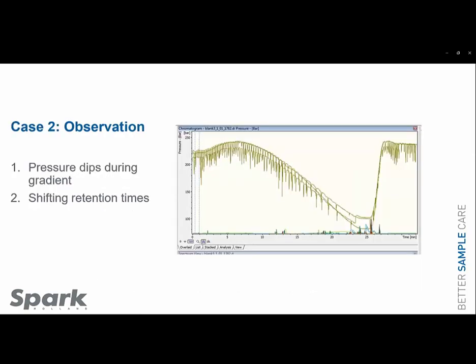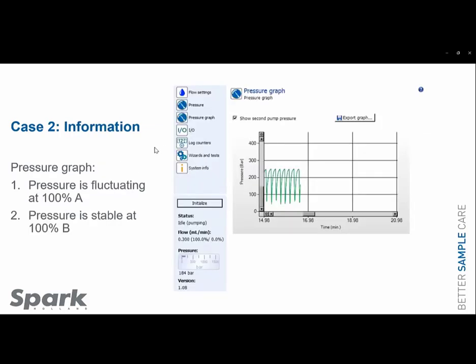We continue with the second case. The customer observes pressure dips during the gradient, as well as retention time shifting. We gather information. We run the pump for 100% A and we run the pump for 100% B. First 100% A. Let's see what's happening. We see pressure dips during this flow action. And this is not good. There's definitely something wrong with pump number A.